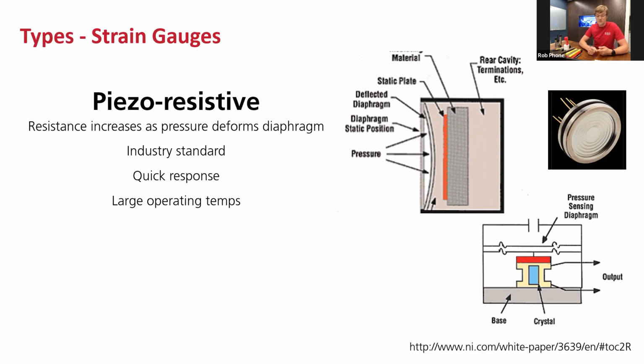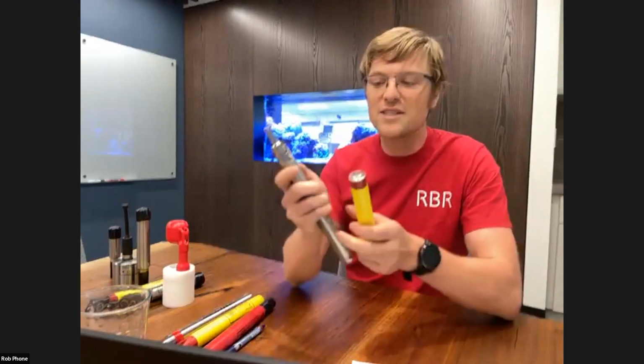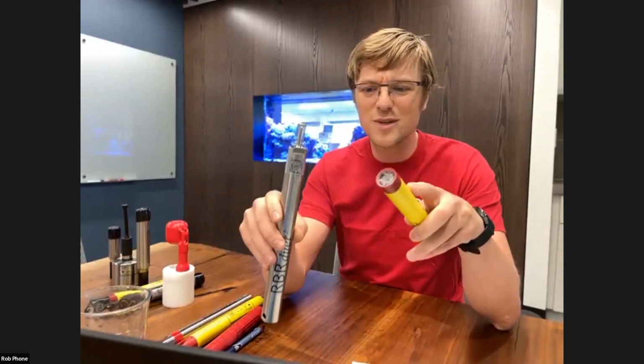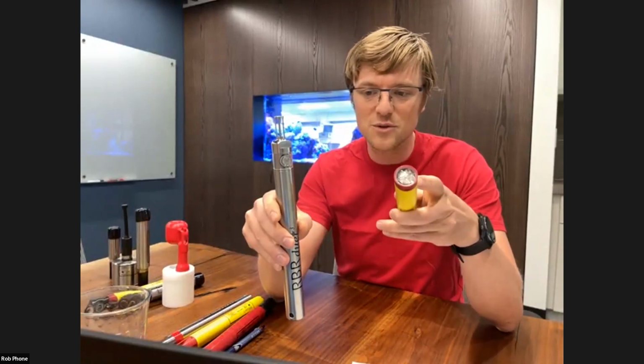They provide a rapid response to changes in pressure, and they can operate across a large variety of pressures and temperatures. Here I have a couple different designs of them. The construction is quite similar. They differ a little bit in the diameter and the materials that are used.